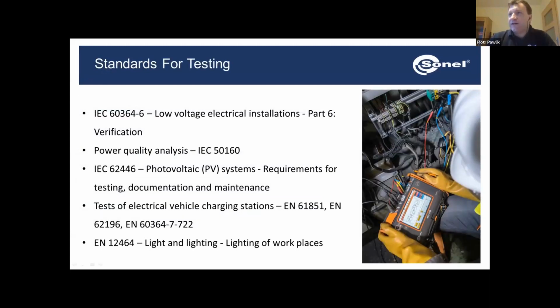If we look at the international standards for testing, we will focus on IEC 60364-6. But here in India, we need to look at the regulation of the CEA, the Central Electricity Authority, and they tell us that we need to follow NEC, the National Electric Code of India, as well as the applicable Indian standards, like IS 732. Luckily for me, for the international environment, IS 732 takes largely from IEC 60364-6.